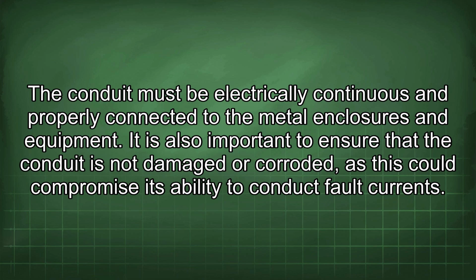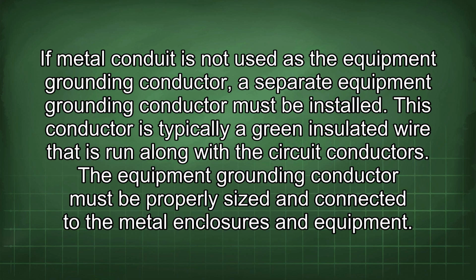to conduct fault current. If metal conduit is not used as the equipment grounding conductor, a separate equipment grounding conductor must be installed. This conductor is typically a green insulated wire that is run along with the circuit conductors. The equipment grounding conductor must be properly sized and connected to the metal enclosures and equipment.